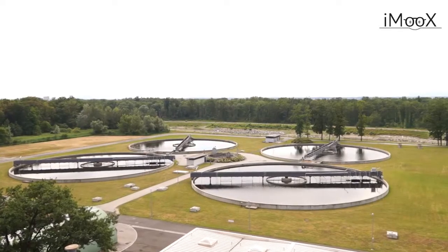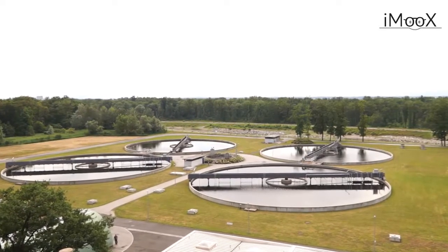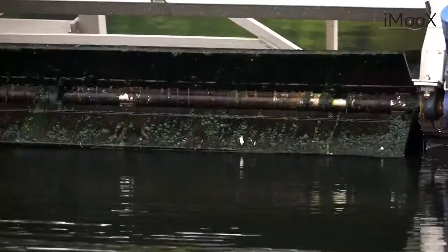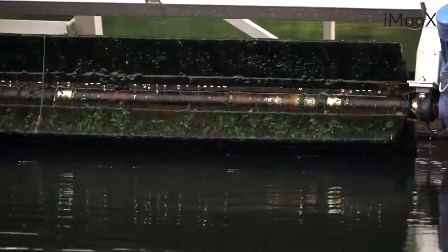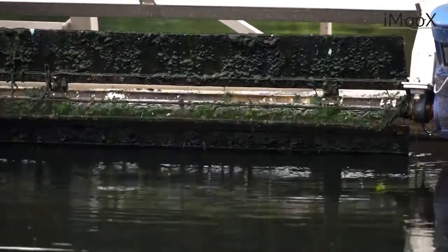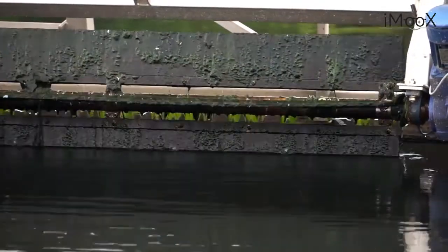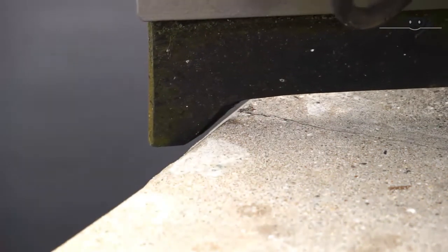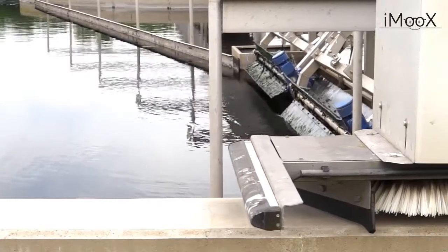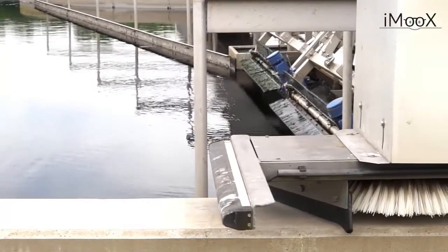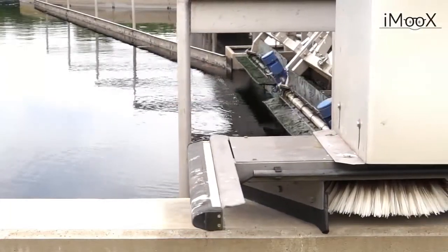Finally, in the after-treatment tanks, the sludge is separated from the water by means of sedimentation. This requires a slower flow rate. In these tanks, the dwell time equals the settling time. Thus, contents of different densities are separated. The sedimentation time depends on the flow rate and the size of the dumping area.